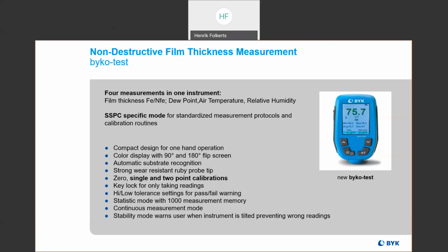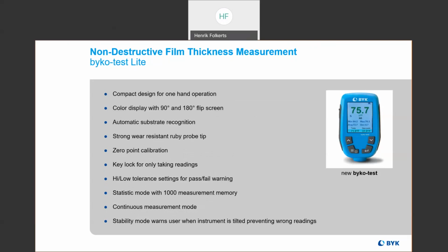And then we also have the Lite version, as mentioned, so it doesn't have quite as many features as the full version. It doesn't do the humidity and temperature measurement, but it still does do both ferrous and non-ferrous film thickness measurements. So of course that means that you can measure the thickness of coatings as long as it is over a metal surface, either a ferrous or non-ferrous metal substrate. So this one also does the screen flip for ease of use, easy one-hand operation. It has that same wear-resistant ruby probe tip, so it's going to last you a good while. This one only does 0-point calibrations and a few other features as well.